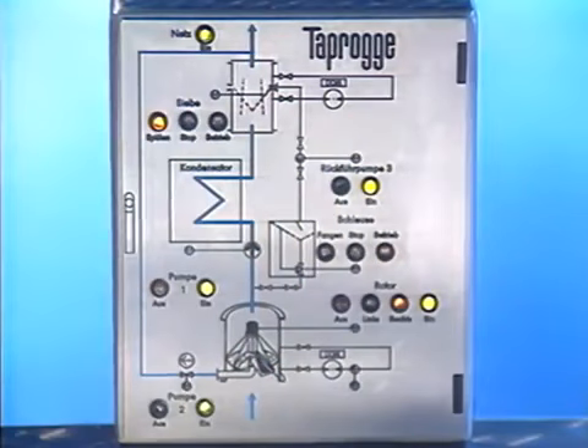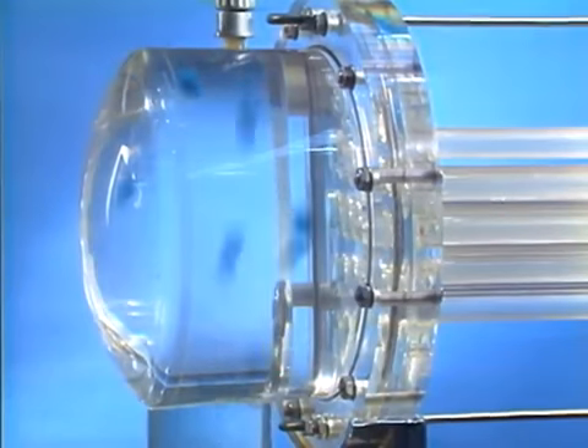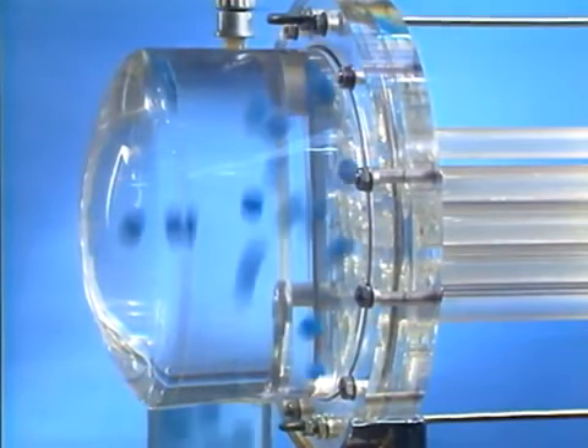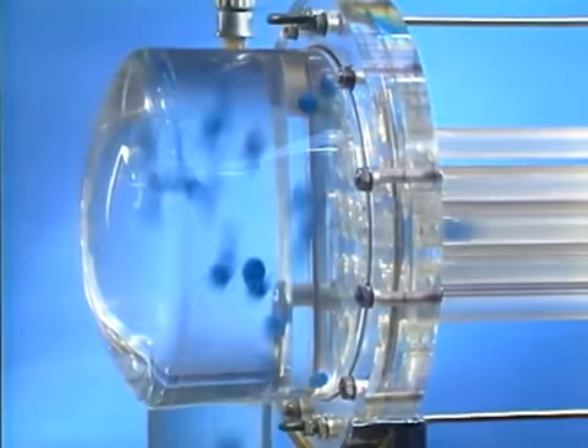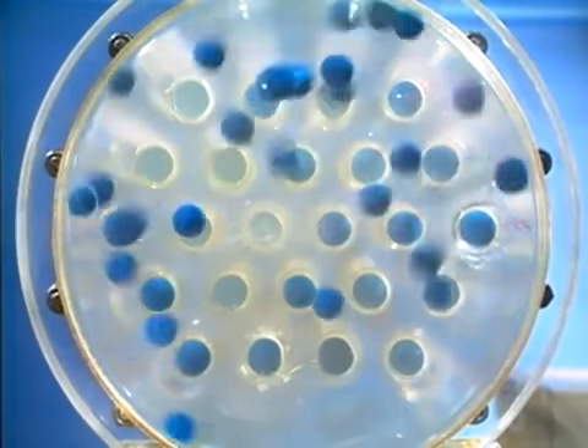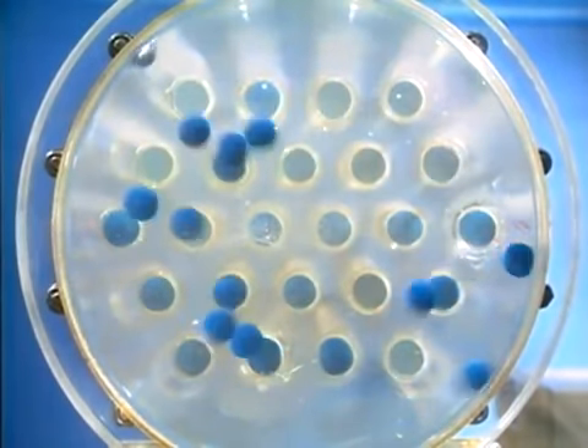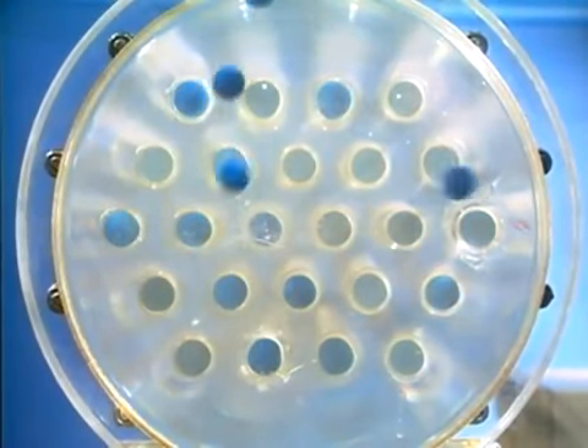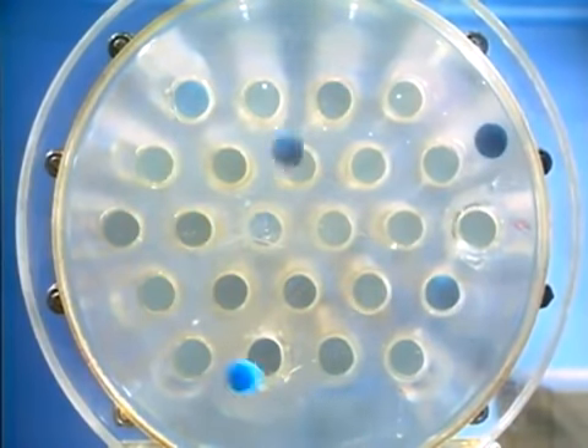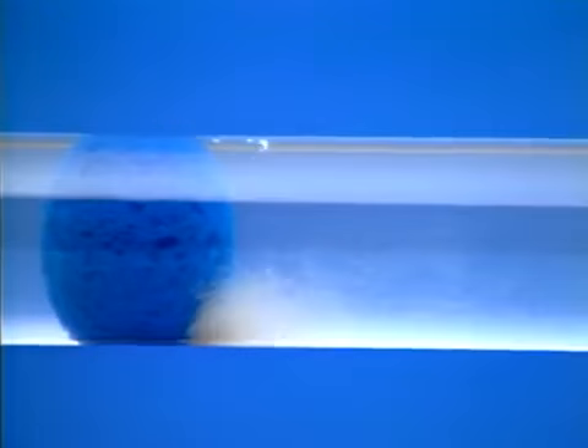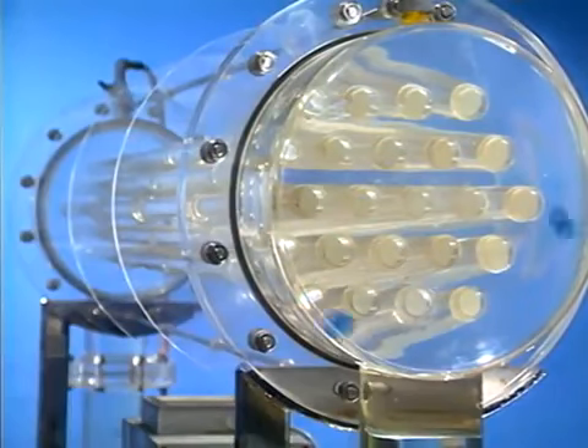A model showing how it works. Sponge rubber balls are injected into the cooling water system at the condenser inlet. The differential pressure across the condenser between inlet and outlet is sufficient to press the balls into the condenser tubes and transport them through the tubes, removing the deposits from the inner surface.